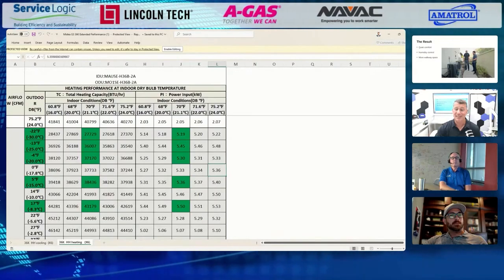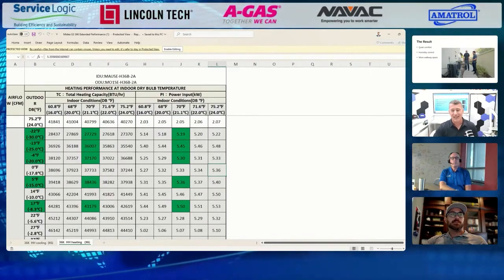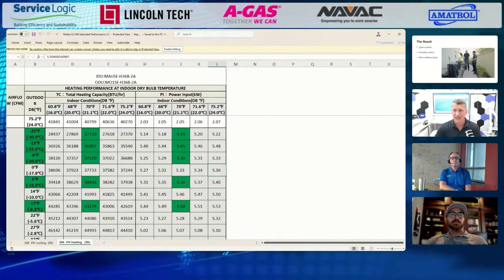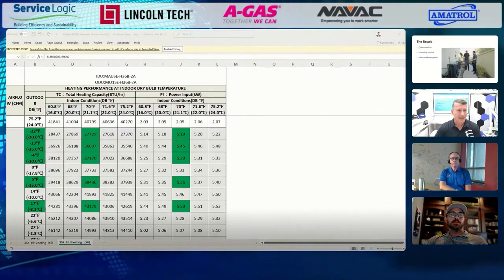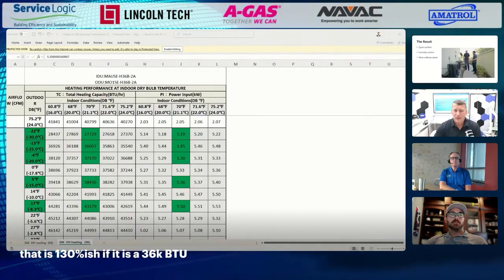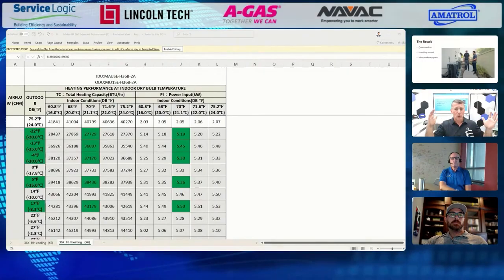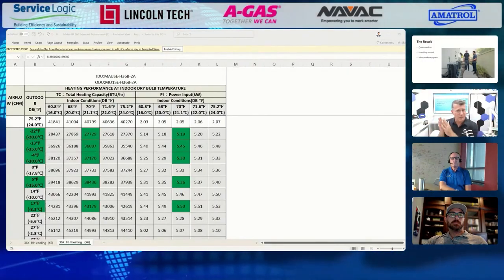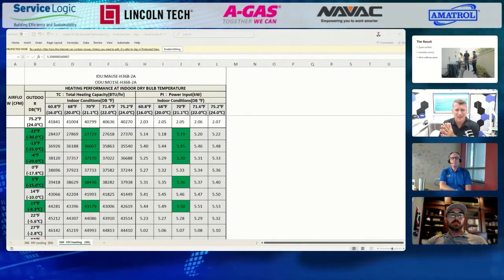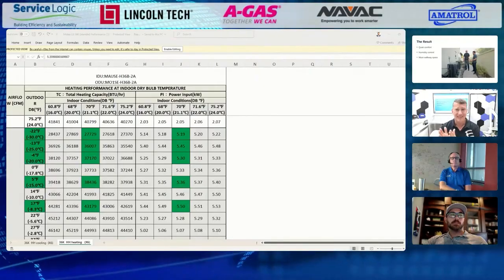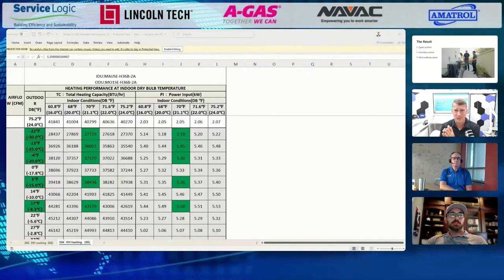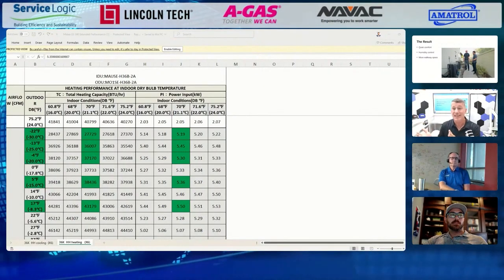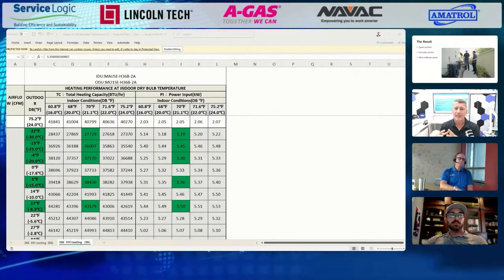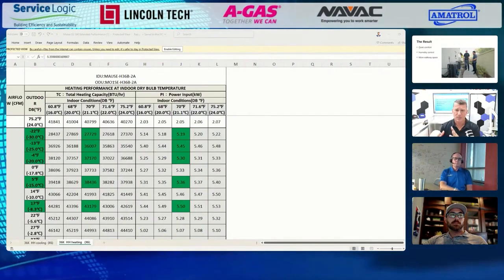This is one of the things we see with a well-designed, well-tuned inverter: because we're running 3-phase motors, we can run a variety of capacity. What one speed could be considered 100%, that might not be anything. We might decide that's just a speed, let's go beyond this speed. It's in managing the compressors properly where we get these capabilities.